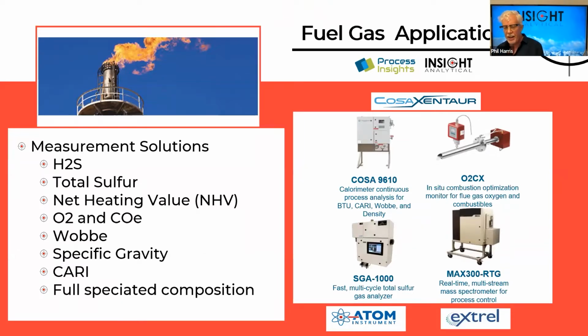So on the fuel gas side of things, when we have a refinery, or it could be a SAGD processing facility up in the Alberta oil sands, or we're producing wells, we'll often use some of the excess gases from processes, whether it's a hydrocarbon stream that's coming off the vapor side of part of my distillation tower, or well casing gas coming back from my SAGD wells. We'll often use some of those gases as a low-cost fuel source for some of our burners. And if we're going to do that, we have to realize that a lot of those gases are highly variable in their composition. Not only that, there are specifications on them for both total sulfur and H2S.